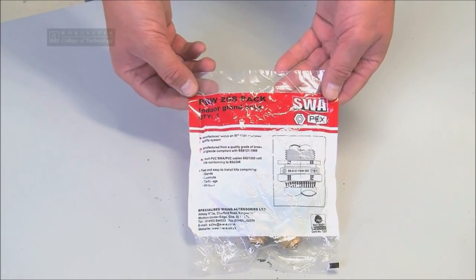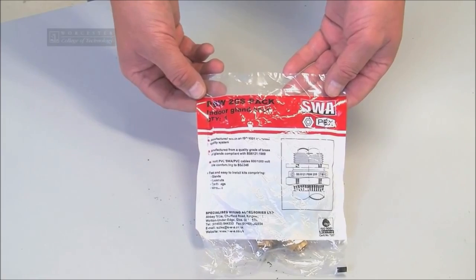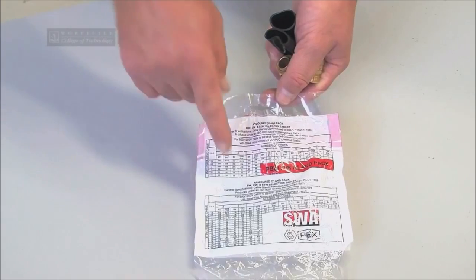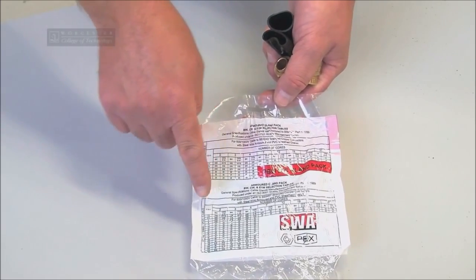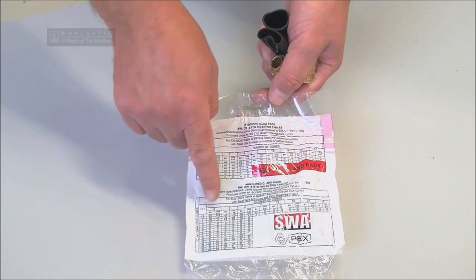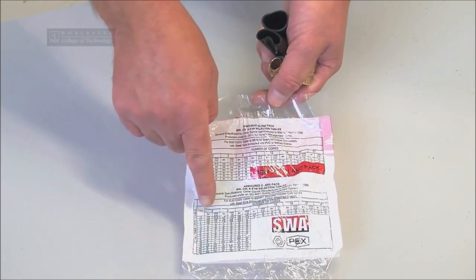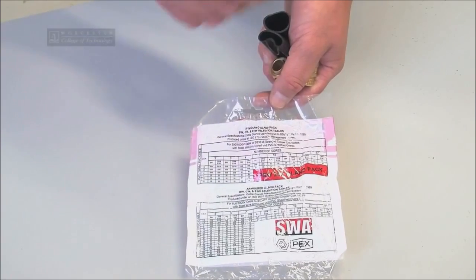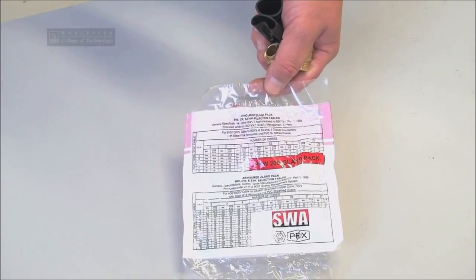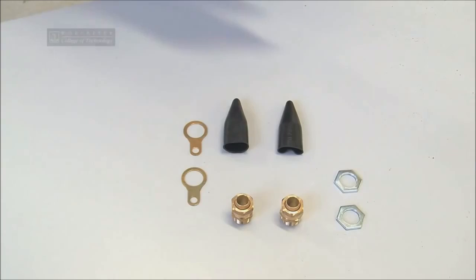This is the S20 gland kit that we will be using. On the back of the packet we have all the cable sizes with respective gland kits that are required, and for the 2.5 we use the 20S gland kit. The gland kit consists of 2 shrouds, 2 glands, 2 20mm lock nuts and 2 20mm earthing tags.